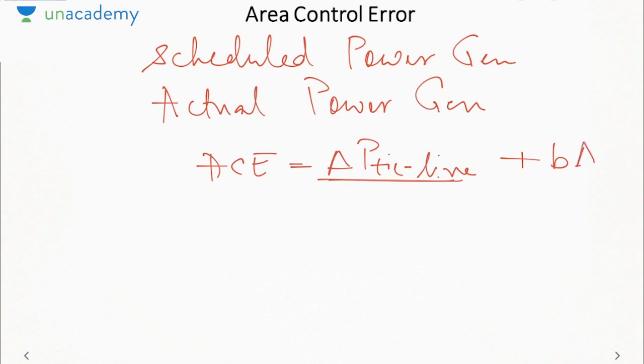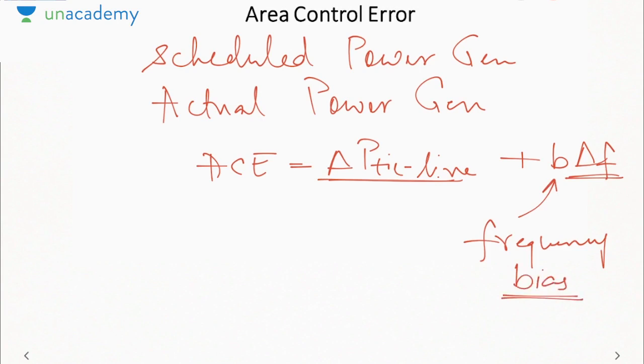Next is B delta F. That is the change in power generation due to change in frequency. B is called as frequency bias. Okay, so this gives me area control error. So what I am saying is generation will change due to two factors: the system drawing power from other generators through the transmission line, and due to change in frequency. So any control system will give certain error. It will not be able to generate the power whatever is the scheduled or the planned quantity.